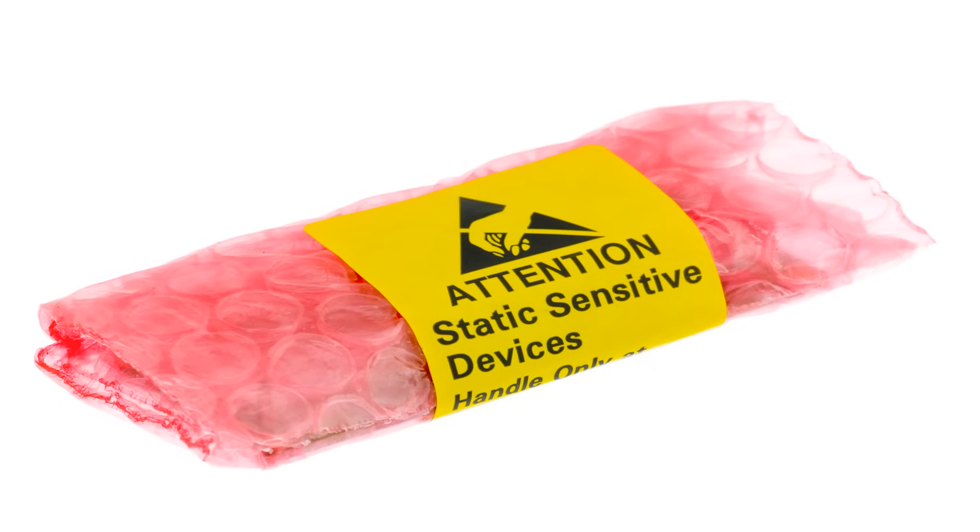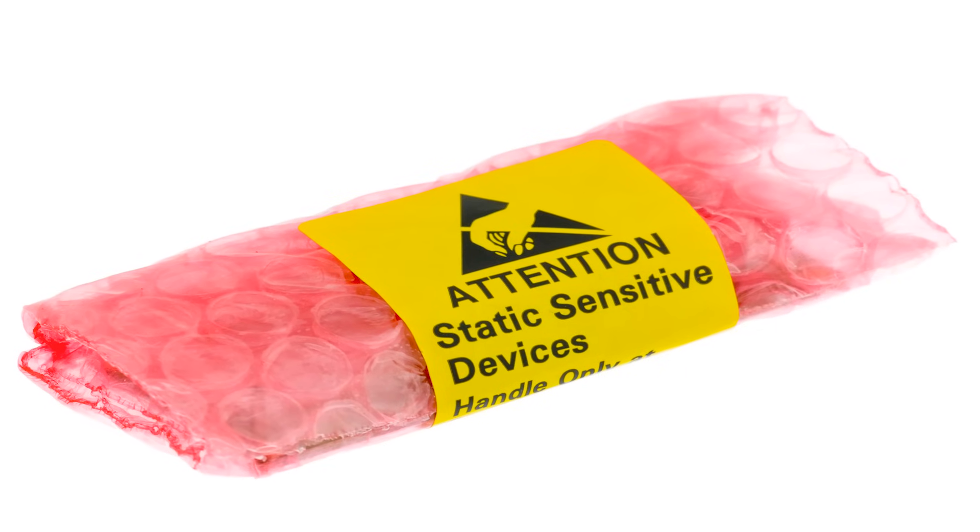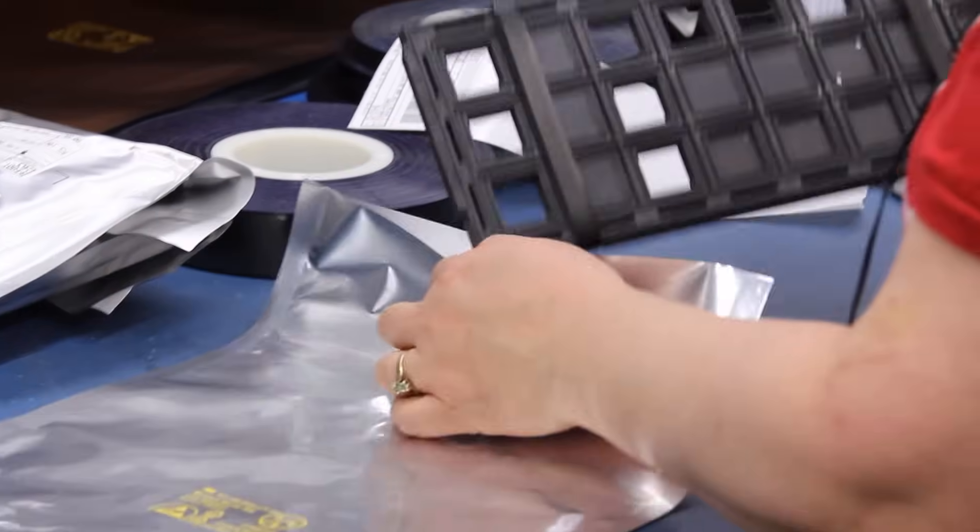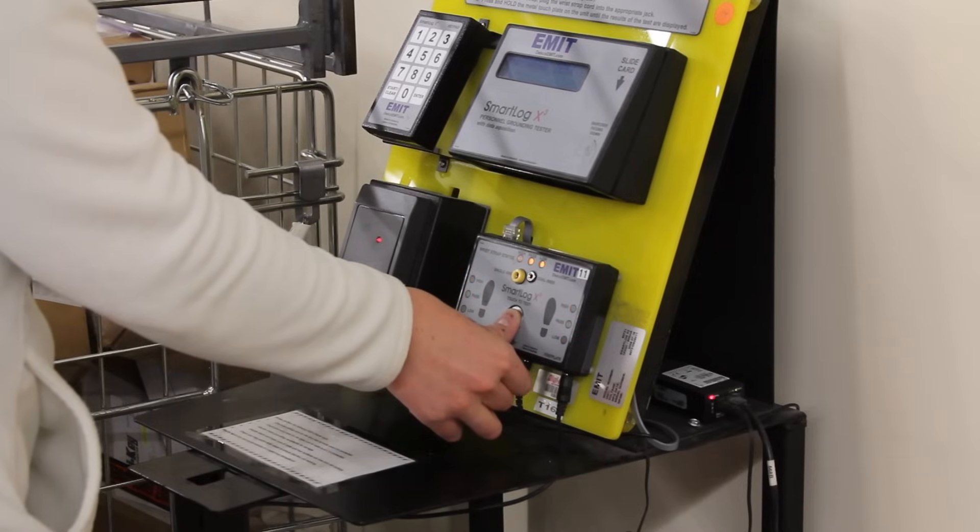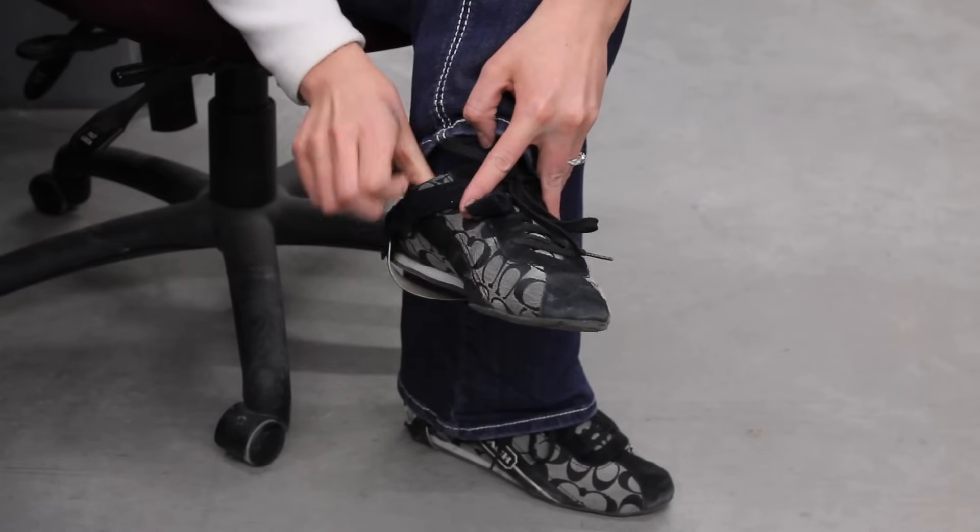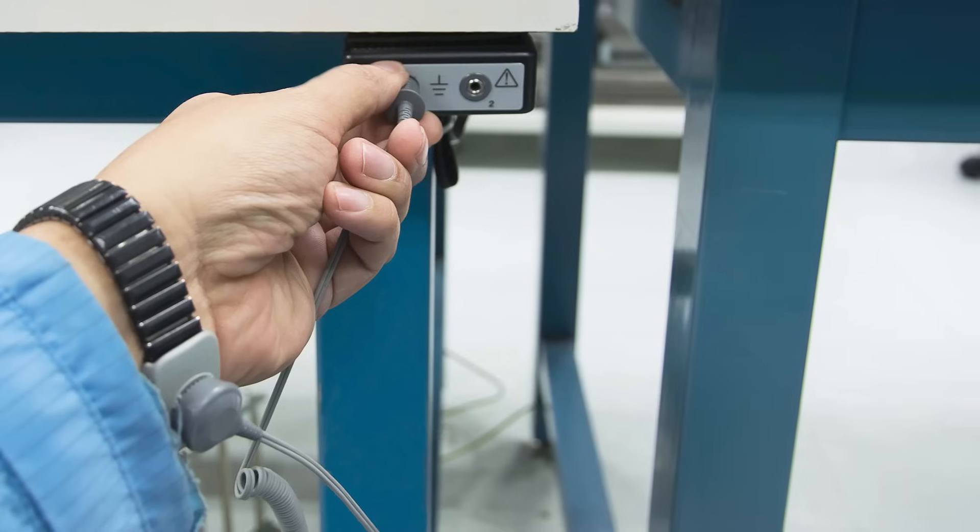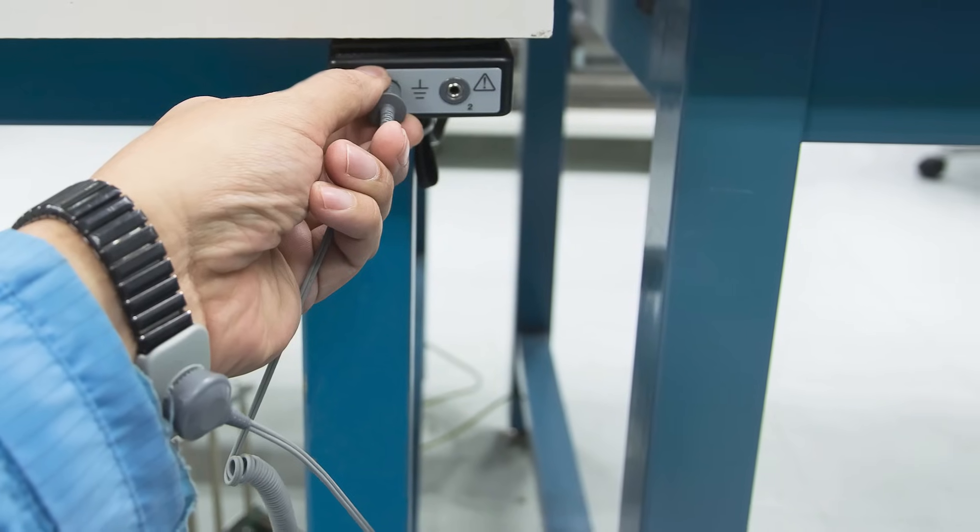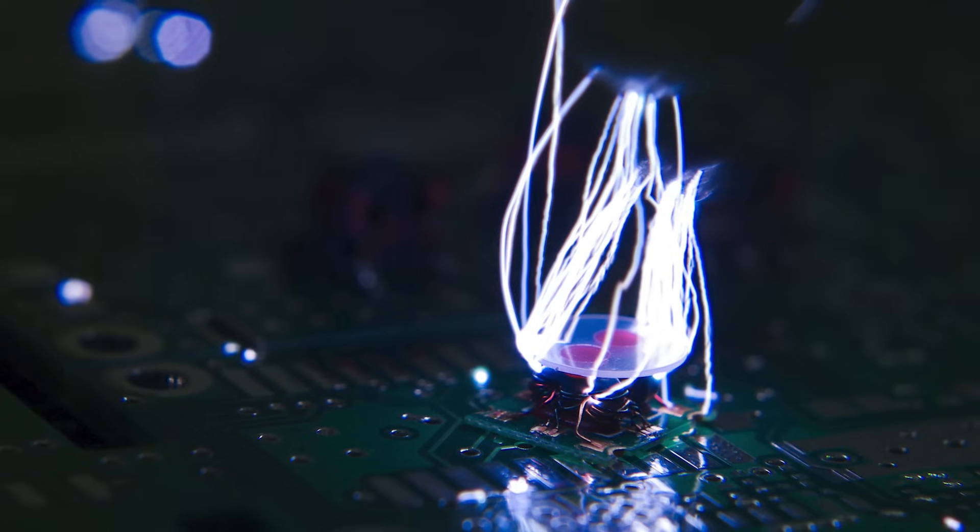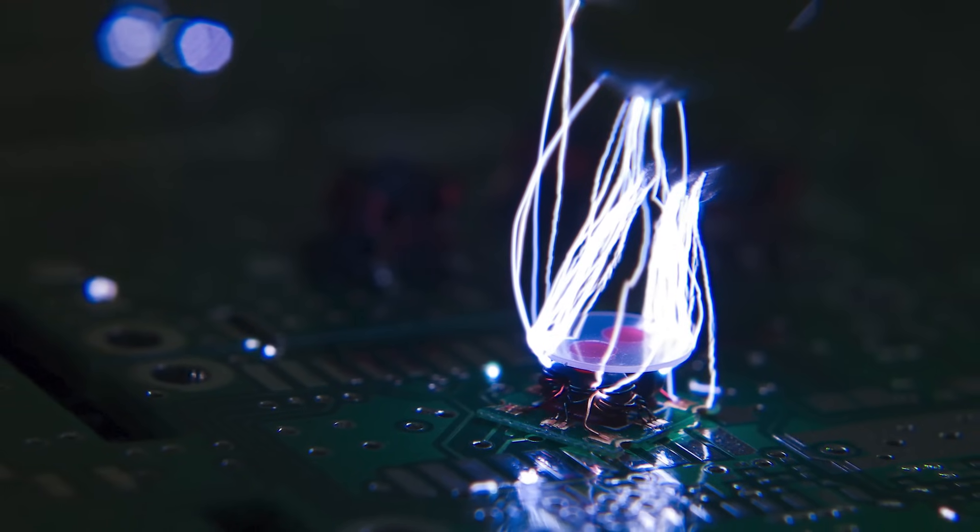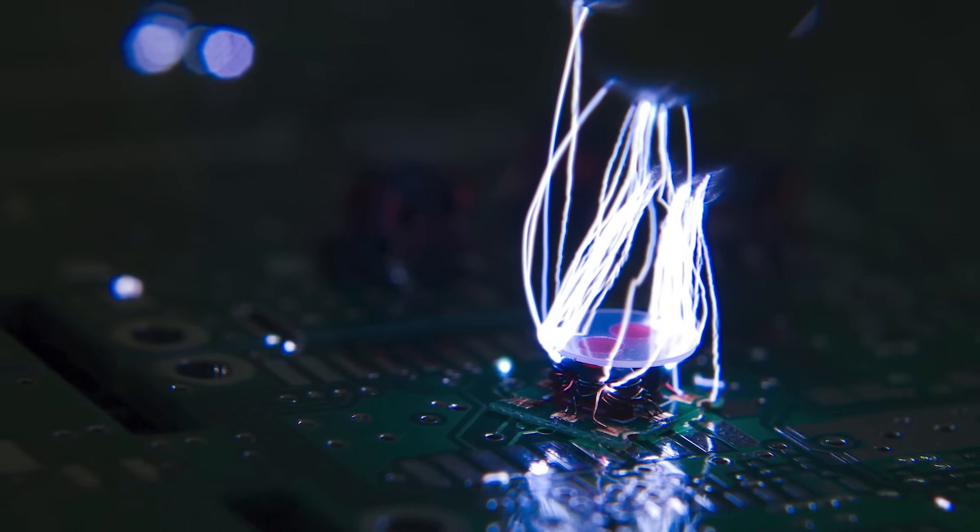Taking proper precautions such as transporting sensitive devices in sealed ESD-protective materials, bonding or electrically connecting all conductors, humans included, in an environment to the same potential as the device or assembly, and removing any unnecessary items from ESD-sensitive workstations that could cause an ESD event will all help keep your sensitive devices safe.